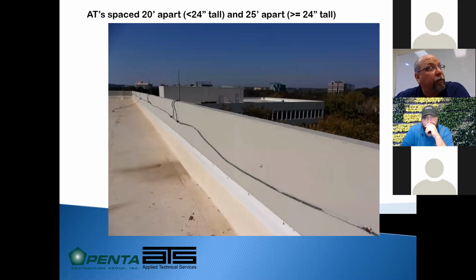The air terminals have to be spaced no more than 20 feet apart if they're less than 24 inches tall. With 24-inch tall air terminals, you can make that spacing 25 feet. The conductor has to be securely fastened every 3 feet. So we have a lot of areas where the fasteners have become detached.